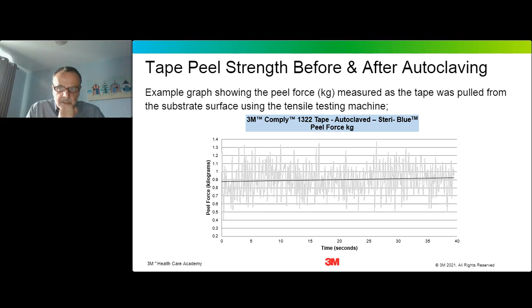Now, this slide is an example of the kind of graph that you would record from the tensile testing machine. And you can see on the left-hand side of the chart is the peel force, and then the x-axis, the horizontal axis, is showing you the time taken to peel the tape from the surface. And you can see that it's quite a noisy signal, and this is quite typical of tape, because as you can imagine, as the tape is peeled from the surface, it will hold and then suddenly give, and then hold again and then give. So it's not a flat continuous process. But of course you can calculate the average peel force from that signal.